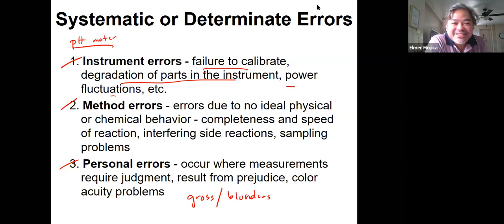And then I realized, oh yeah, I calibrated. And when I look at the calibration, the toluene also shifted by 5 wave number. So that means the result that we have is useless. It doesn't show anything. Because if there's a shift in the standard by 5 wave number, your sample will also have a shift of the same number. Okay? So there is already what we call an instrument error on that thing.